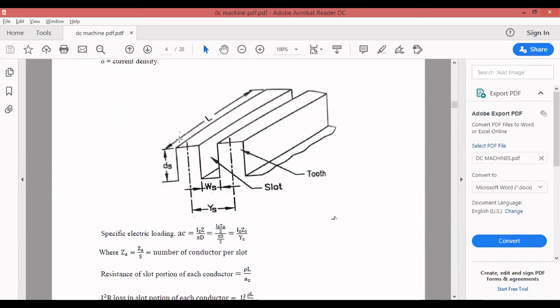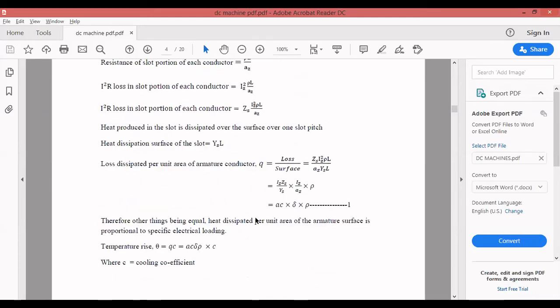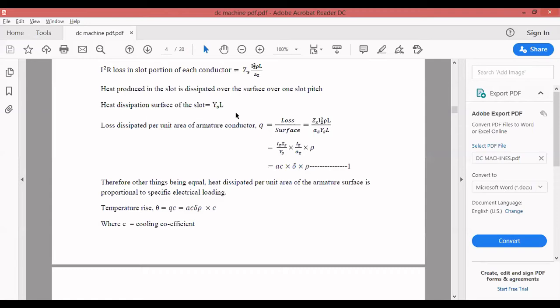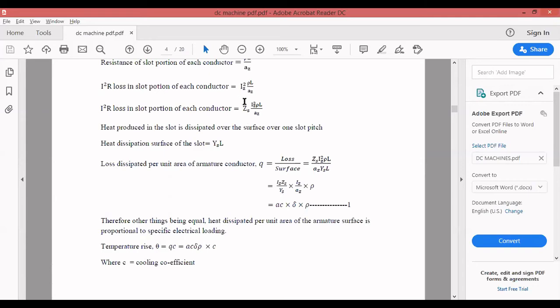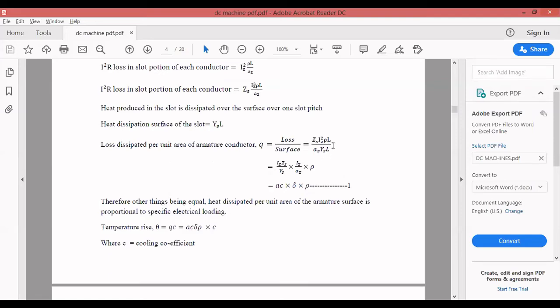If you go for a higher rating machine, the speed will be higher and ventilation will be better, so dissipation of heat will be faster. Third factor is voltage. In a high voltage machine, larger space is required for insulation and therefore less space is available for conductors — around 60% for insulation and 40% for conductors. This means in a high voltage machine, the space left for conductors is less, and therefore we should use a small value of ampere conductors per meter.